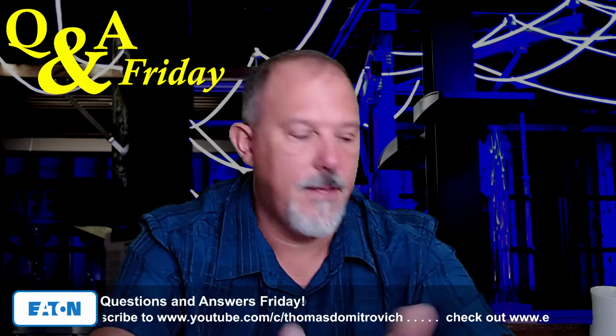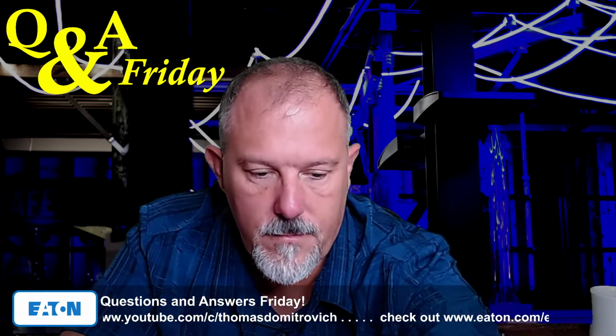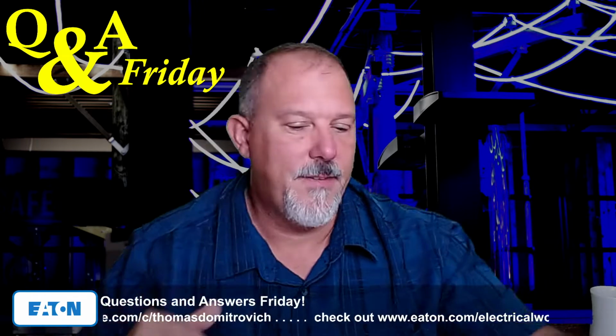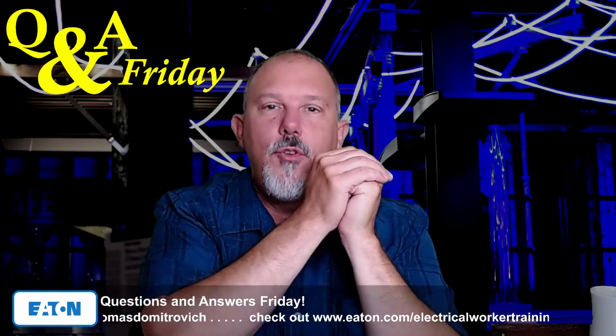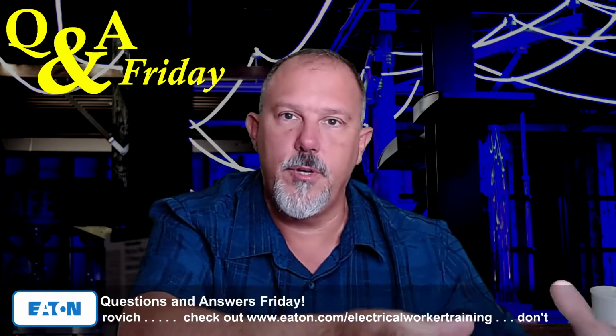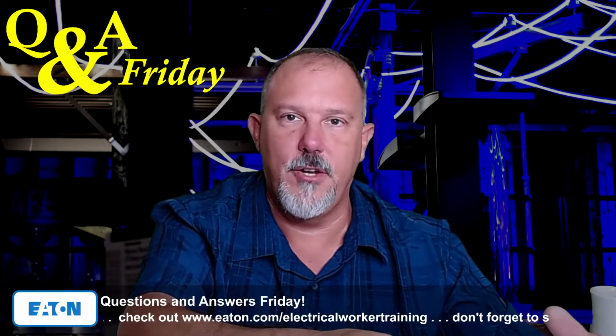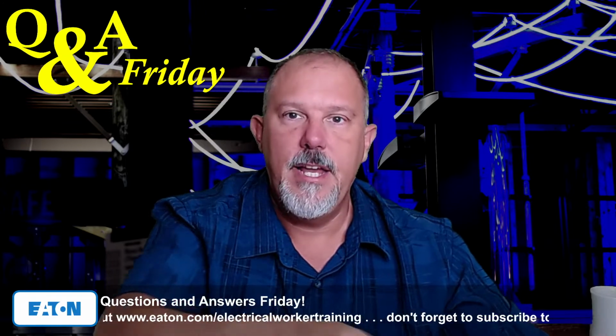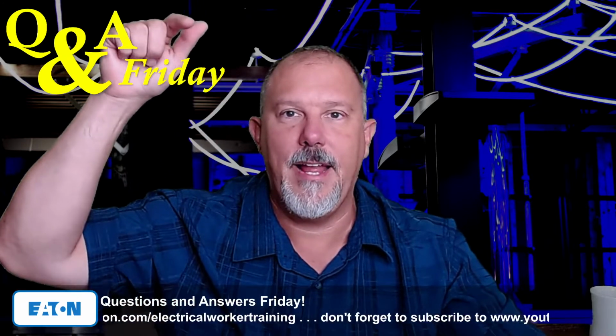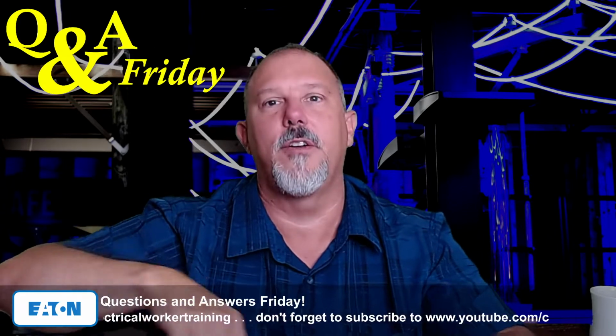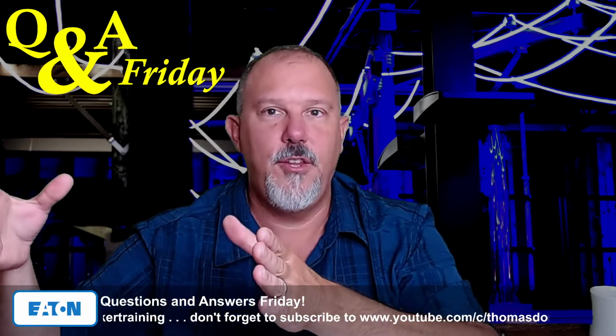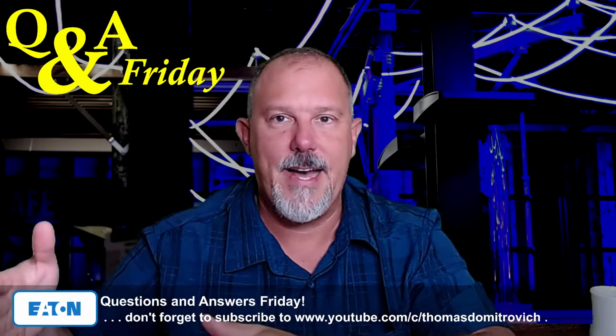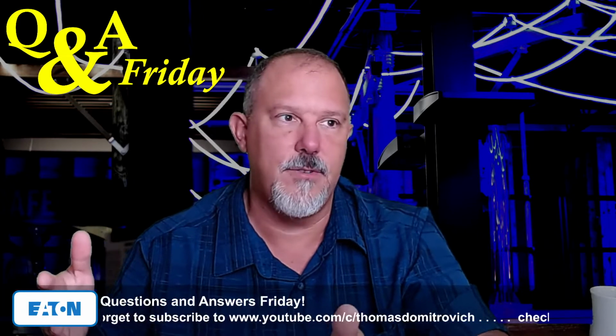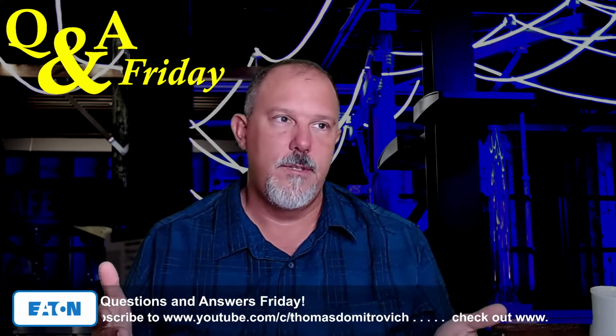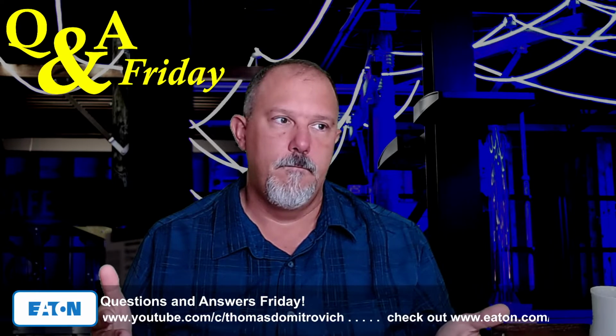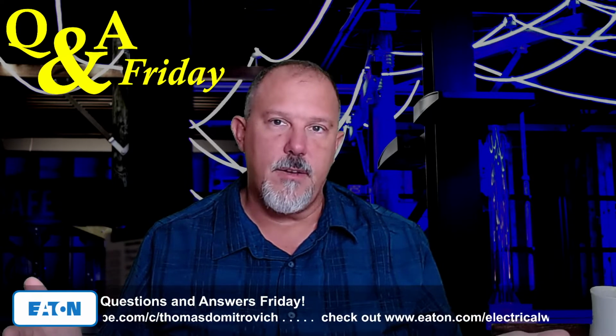Let's say I don't even have to do the math. Let's just say that you are calculating it out and you didn't add the 1.25 in when you calculated all your loads, and they're all continuous loads. If you took and increased the size of the circuit breaker by 1.25, then you've protected the conductor with that, even if you've adjusted it down, you're still at 80% on the breaker.